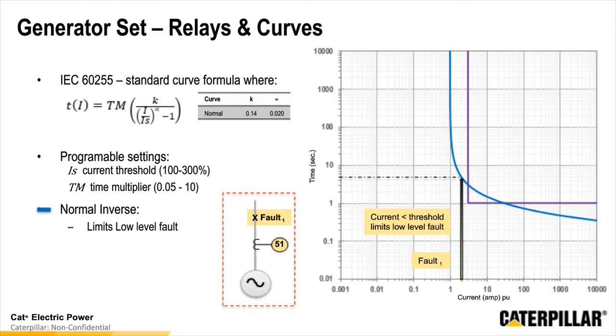The overall aspect of this now is that what it does by having a curve is it gives us the ability to have a little bit more room and a little bit more power within that area left of the definite time curve setting. So it's the time rated. We can have longer time trips and be able to provide, in this instance, we're showing the 200% fault again, and the fault occurs and is tripped off at 5 seconds rather than providing it continuously.